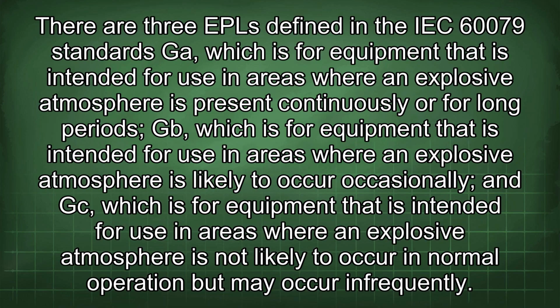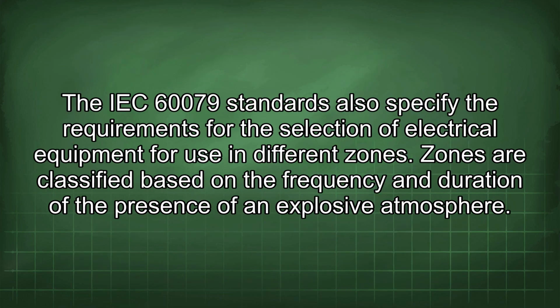There are 3 EPLs defined in the IEC 60079 standards: GA, which is for equipment that is intended for use in areas where an explosive atmosphere is present continuously or for long periods, GB, which is for equipment that is intended for use in areas where an explosive atmosphere is likely to occur occasionally, and GC, which is for equipment that is intended for use in areas where an explosive atmosphere is not likely to occur in normal operation but may occur infrequently.